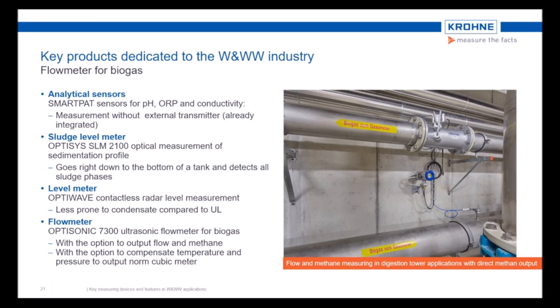Another key device out of the flow portfolio is the ultrasonic flow meter Optisonic 7300 for measuring biogas. The unique feature here is the option to output the flow and methane, which brings additional value for the operators because they can immediately monitor the proper gas production in a co-fermentation station. In this connection, the operator can decide about feeding the right quality of fat, which they have buffered, to control and ensure always the best gas production within the process.